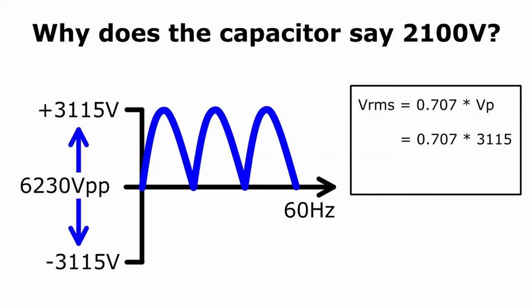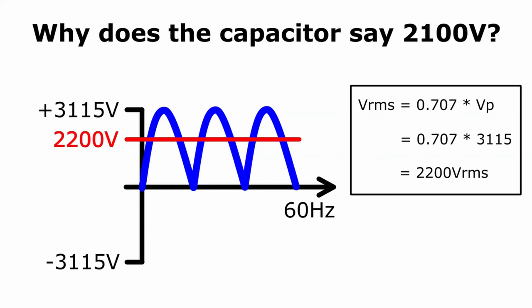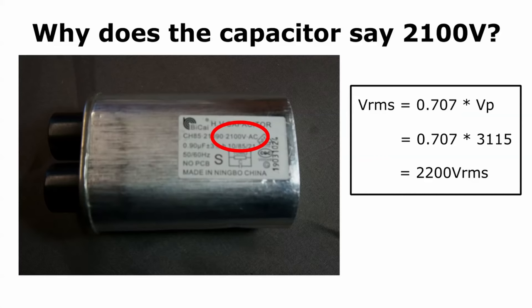For our transformer, the peak voltage is 3,115 volts. So the DC equivalent is 0.707 times 3,115, or 2,200 volts. The RMS subscript reminds us that this is a DC equivalent voltage. I've marked this RMS voltage on the graph. With the right circuitry, we could cause this transformer to do the same amount of work as a 2,200 volt battery.